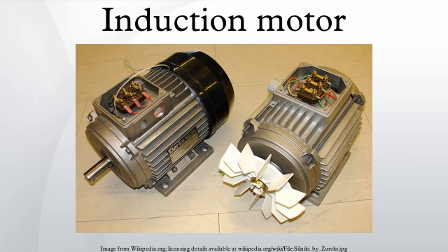Over a motor's normal load range, the torque slope is approximately linear or proportional to slip because the value of rotor resistance divided by slip dominates torque in a linear manner. As load increases above rated load, stator and rotor leakage reactance factors gradually become more significant in relation to such that torque gradually curves towards breakdown torque. As torque increases beyond breakdown torque, the motor stalls.